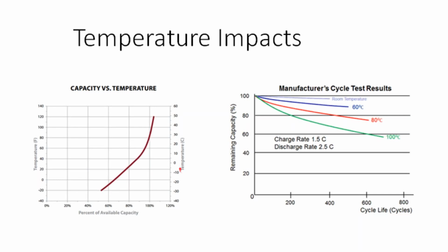As far as the batteries themselves go, if they get hot, it's not good for the battery. They degrade faster at hotter operating temperatures versus room temperature. So this is for a lithium ion battery, but it's true for lead acid as well. They'll actually gain a little bit of capacity at hot temperatures, but that still doesn't mean it's good for the battery. On the other hand, with batteries, you don't want them to freeze.